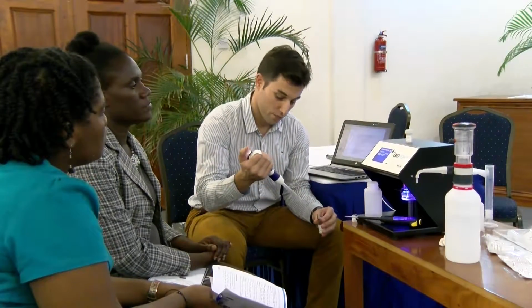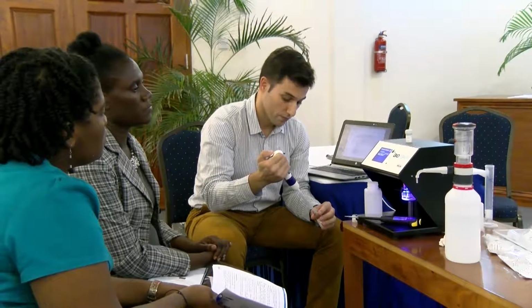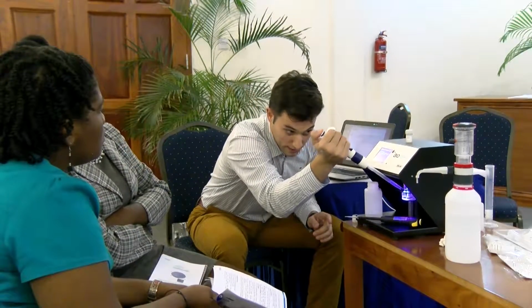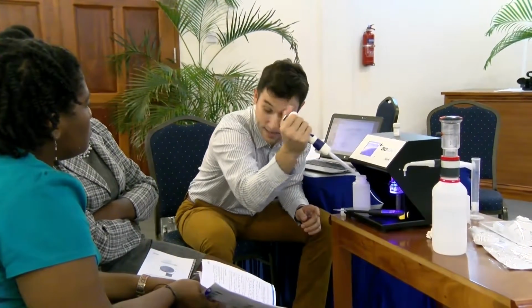You'll see how the current is quite stable. Normally, the device doesn't use the whole time. If the current is stable enough, it will ask to make the addition earlier. It depends on the stability of the signal. Okay, press continue and add 2 milliliters of standard. It's important to press continue, and after pressing, make the addition, because in this moment the device is detecting the zero, and now it will detect a change in the conditions.